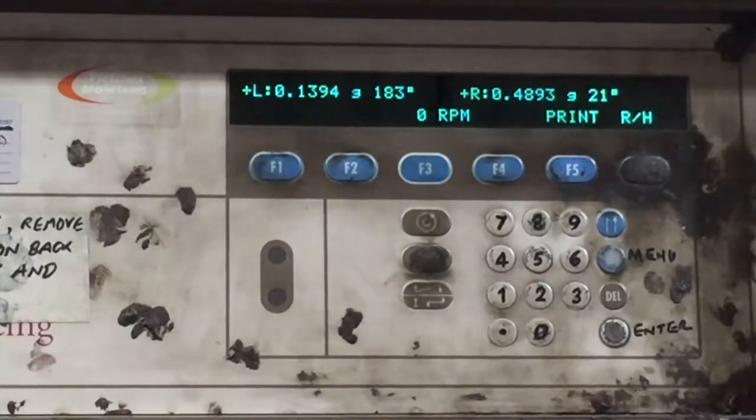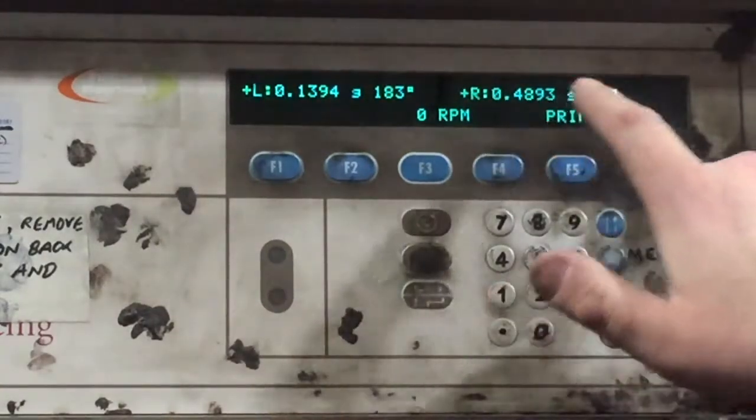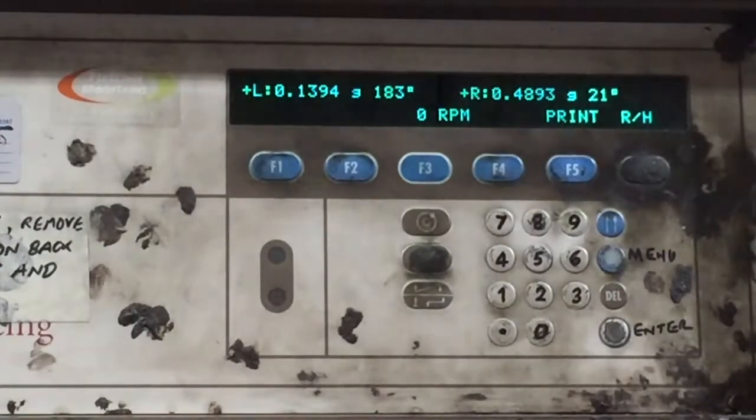After the first test run, what we can see here from the printout from the balancing machine is that we are acquiring almost half a gram at 21 degrees. The engineer will now add that weight and will take out another run so we see which balance grade we have achieved.